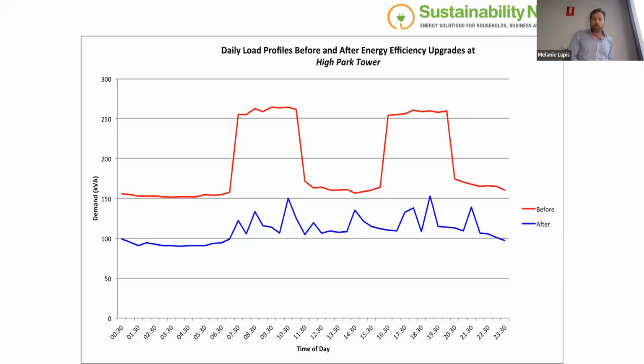So this is what their demand profile looked like before and after. You can see the car park fans. They were running for crazy times, from 6:30 in the morning to 10:30, and from 3:30 to 7:30. Just insane, massive overkill. Look at the demand difference here: 150 kVA was their base load, to 250 kVA up in the middle of the day. So there's 100 kilowatts of extra load there that we just chopped out.